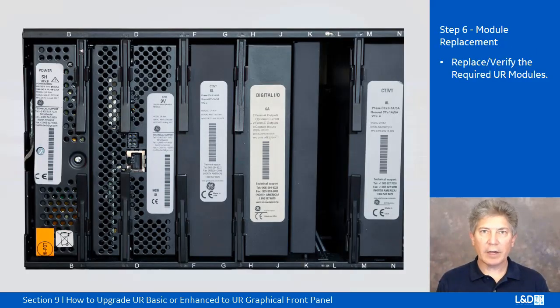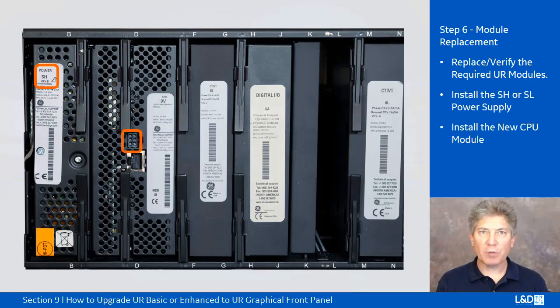Next, let's verify and or replace the required UR modules. Install the SH or SL power supply and install the new CPU module with the additional connector. Now, there's a note here. It's recommended to use both handles when extracting or inserting these modules.